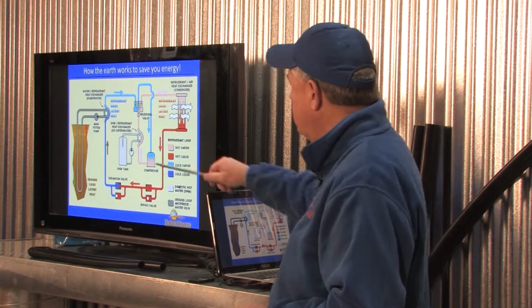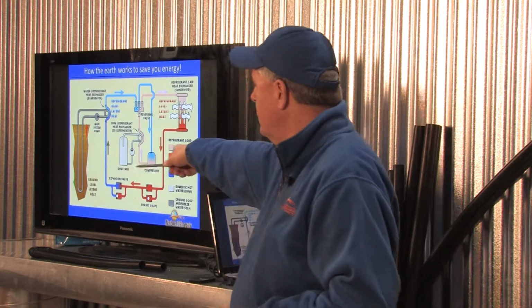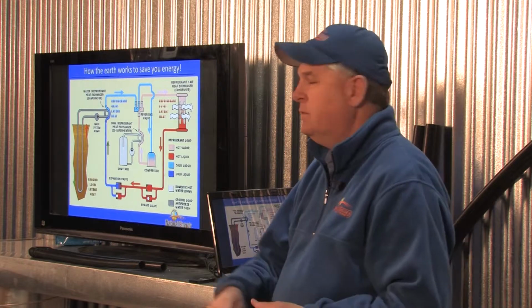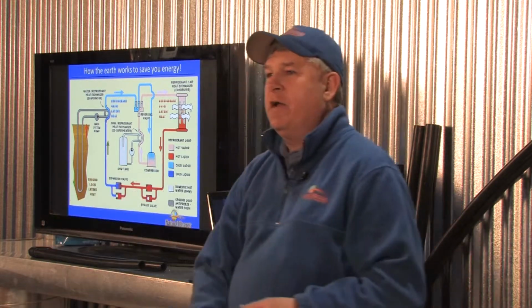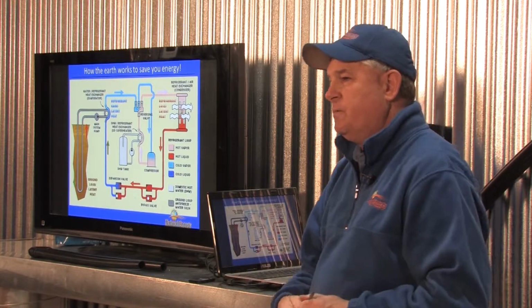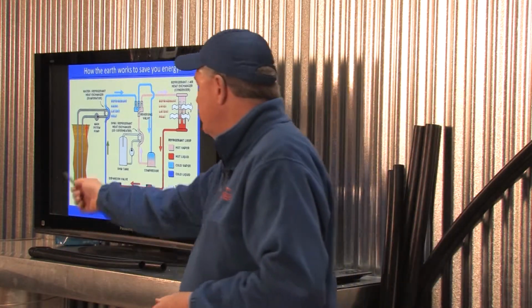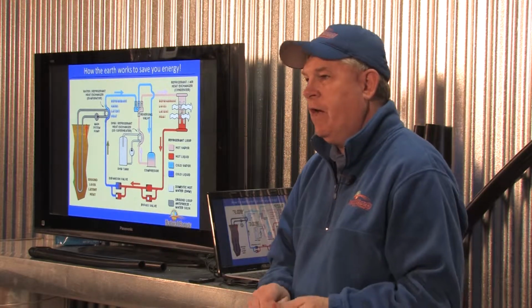Starting at this compressor, which can only turn one direction, when the gas comes out of it, it's just as hot as before. But now when we hit that domestic hot water, we want to take all we can, because we're about to throw the heat away. You now have free hot water. Anytime you're in cooling mode, you have free hot water, because we're about to throw the heat away anyway. By definition, when we use a waste product, it's free.